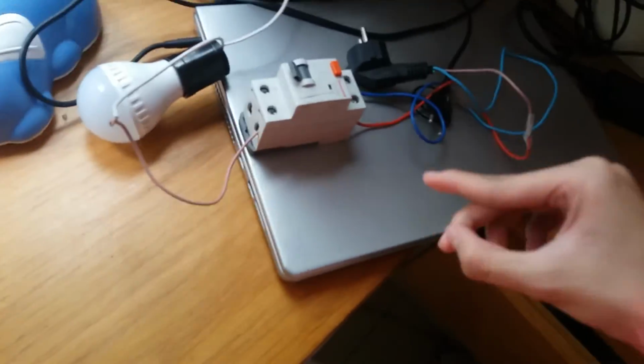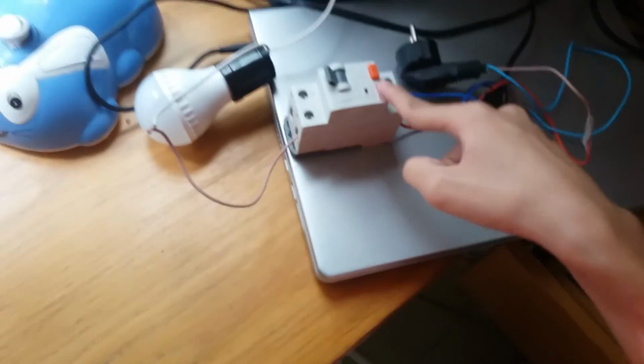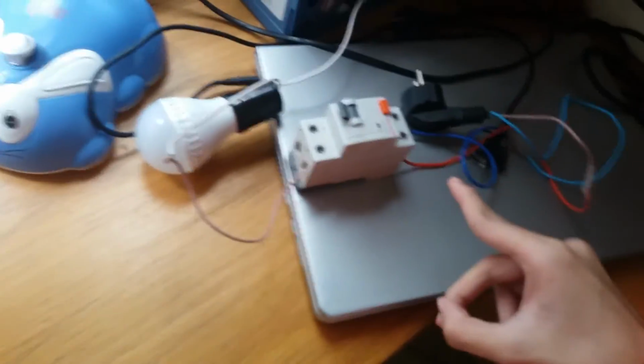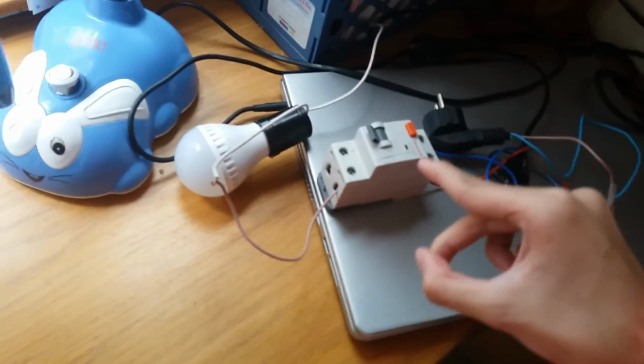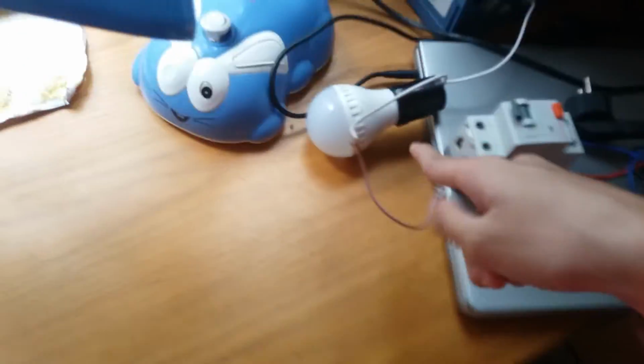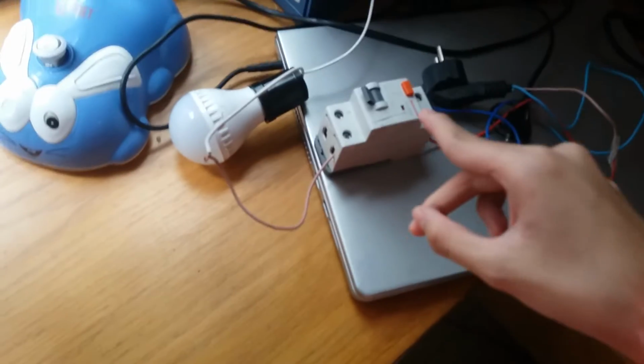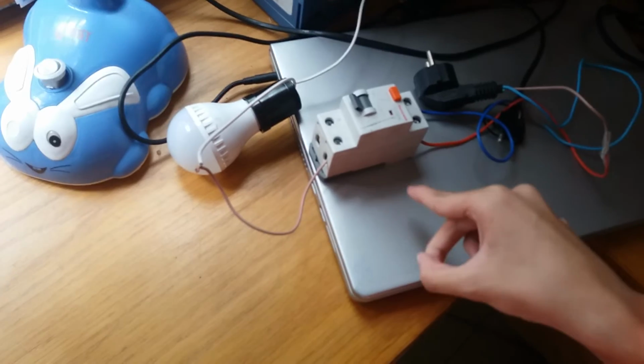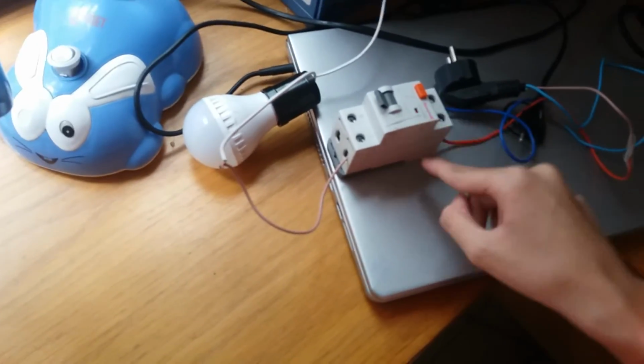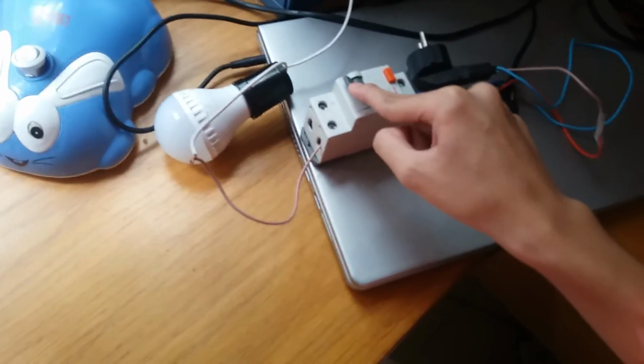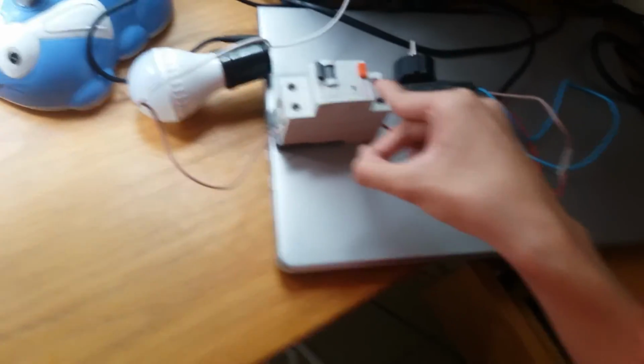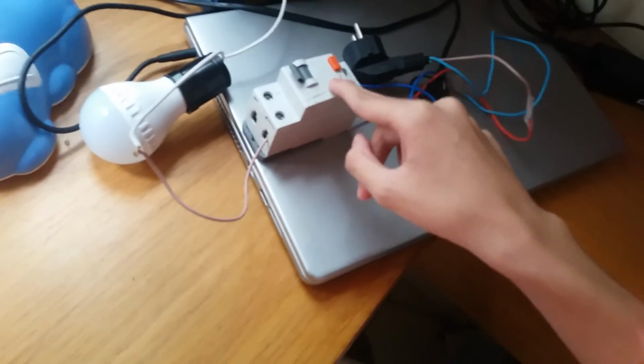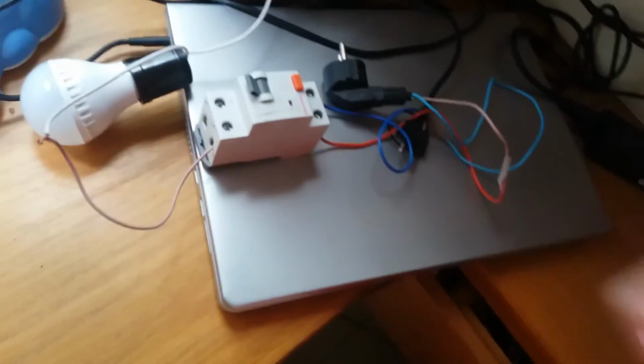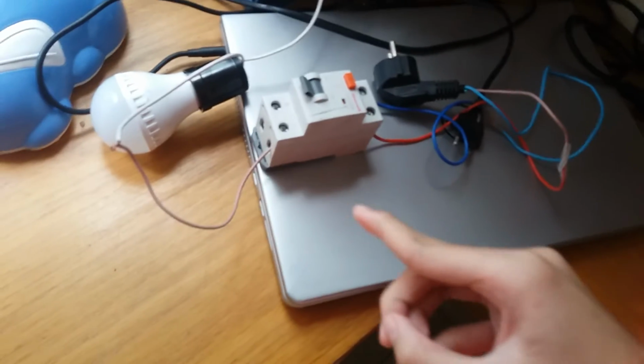You can apply the first way, pressing the test button, or the third way, using the light bulb to test. You cannot apply the second way because the leakage current is not enough to trip this CB, since it's lower than 30 milliamperes, so the CB cannot trip.